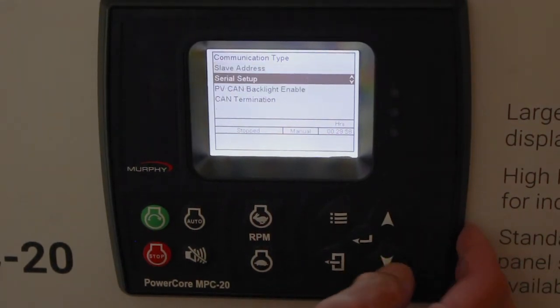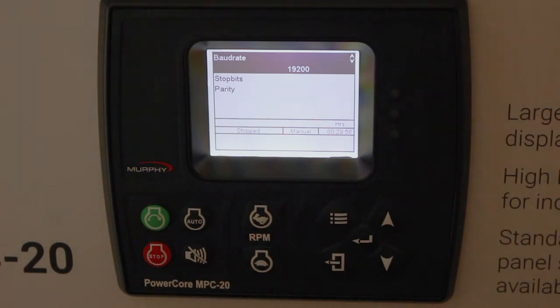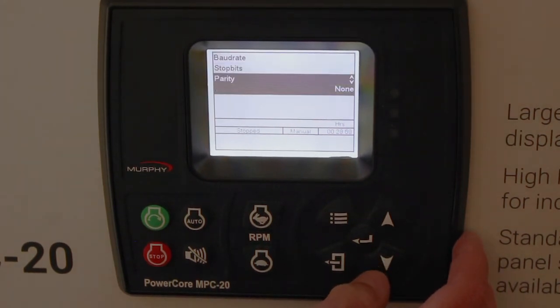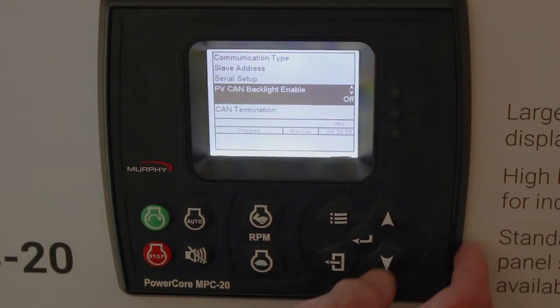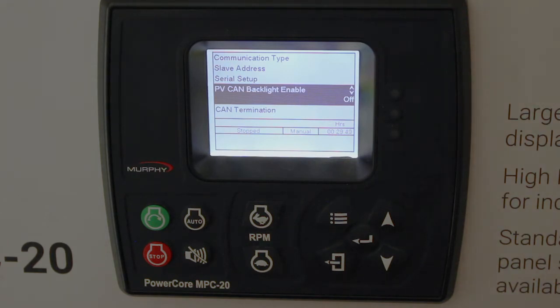In the Serial Setup section, the baud rate is 19.2 — you can change that; it's the default. Stop bits is 1, parity is none — you can change that to parity if needed. Those are good defaults. PVA backlight: if you're using the PVA option on the RS-485 port, you can have the PowerCore turn on the backlight to the PVA gauges if you want — it defaults to off.